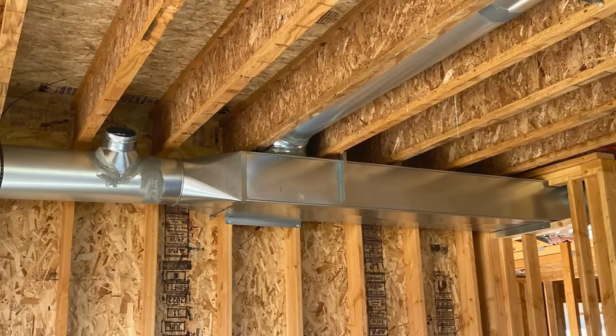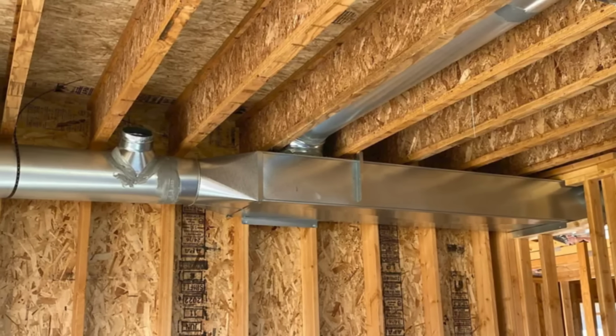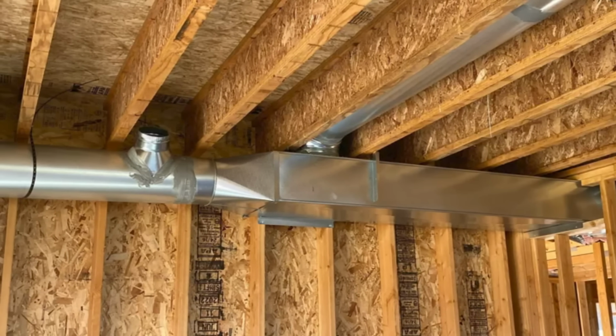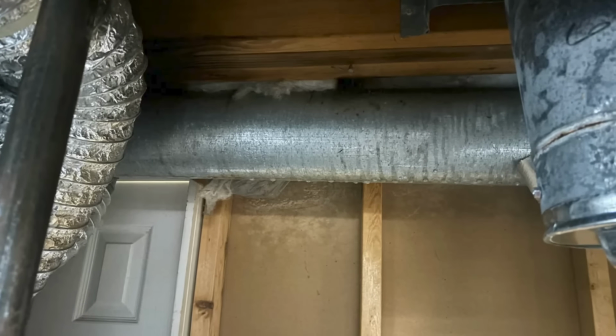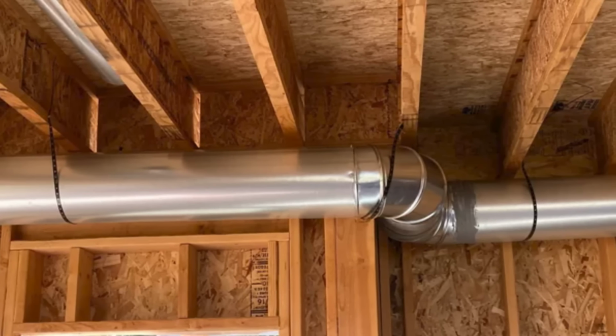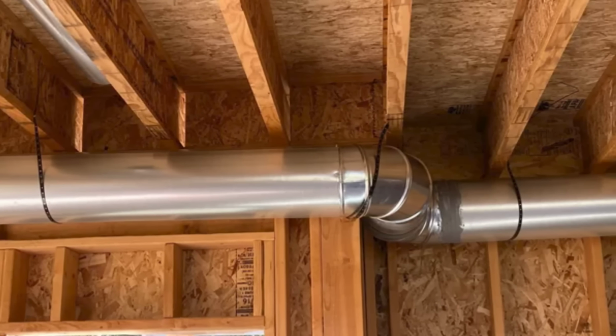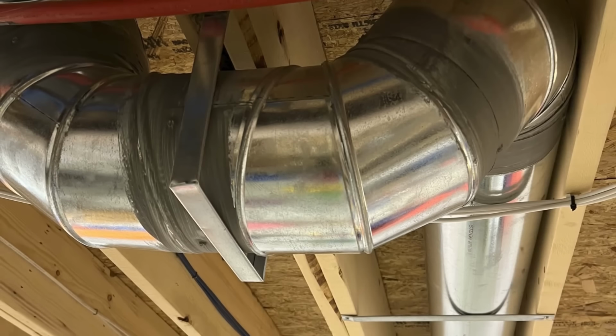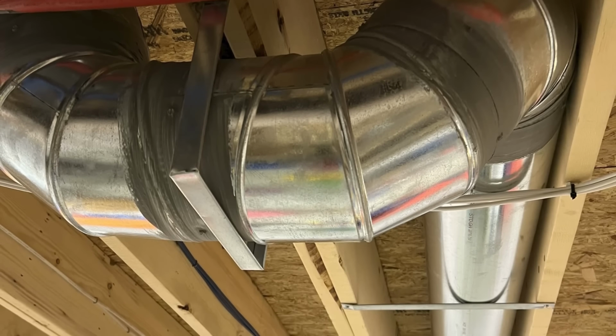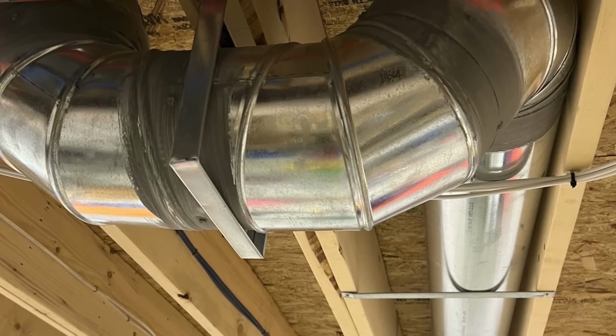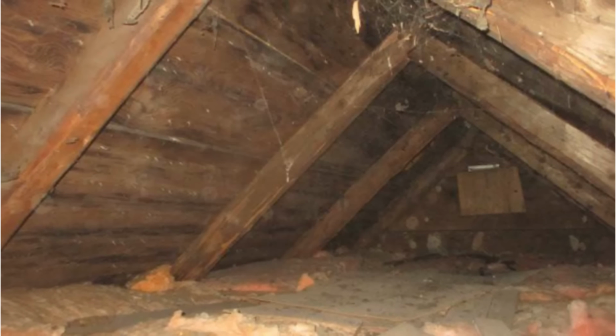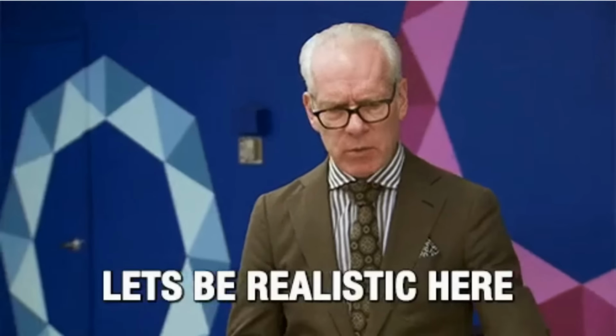By keeping the ductwork below the ceiling's air barrier, the ductwork is kept within a stable, conditioned environment, significantly reducing the potential for condensation on those ducts. Not to mention, if the ducts leak slightly, they simply leak into the house they were already trying to condition, resulting in virtually zero energy or moisture penalties, and you won't compromise your indoor air quality by sucking air from the unconditioned attic space. But let's be realistic.